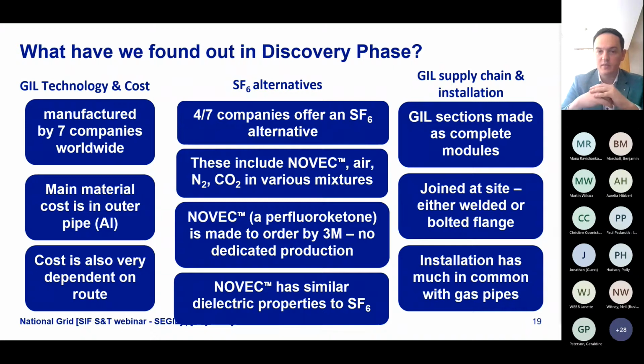Installation itself is very similar to gas transmission pipelines, and we can leverage the benefits of gas transmission here, experience in construction and operation. Although gas transmission runs at much higher pressures, 100 bars, where normal GIL or GIB systems run at about 7 bars. So it's a bit different, but from the construction point of view, it's very similar in this sense.